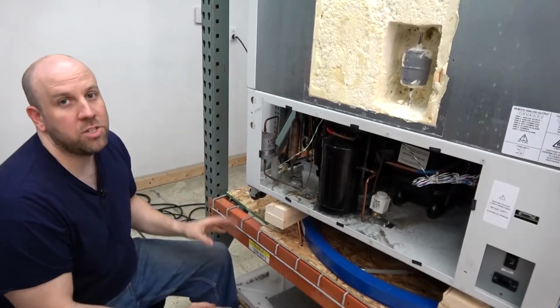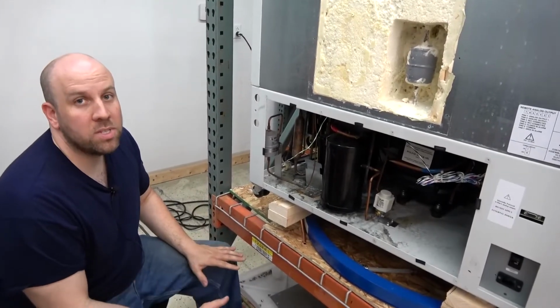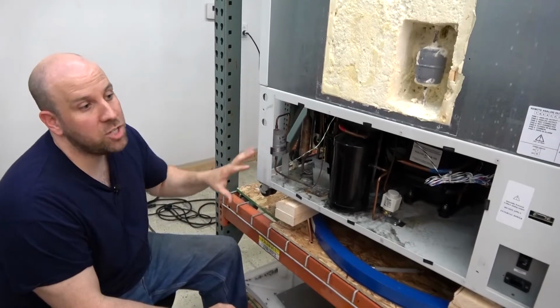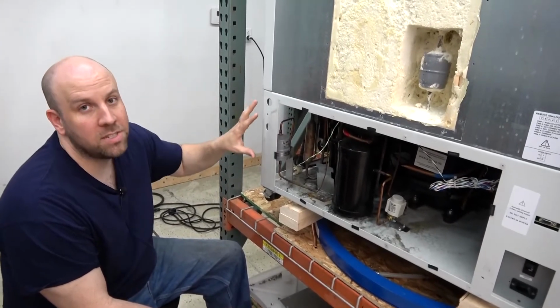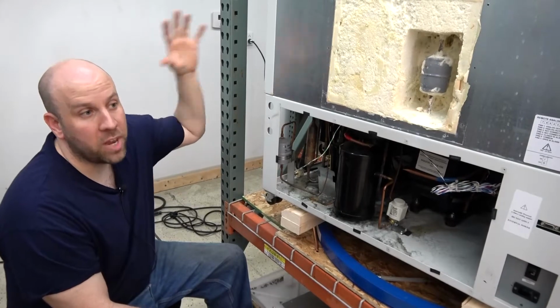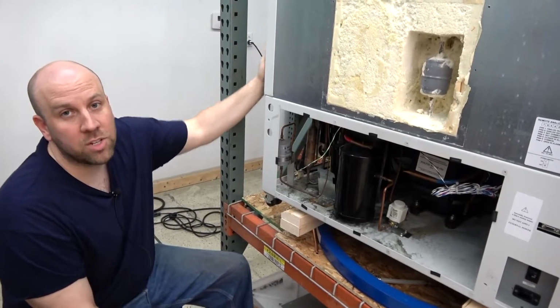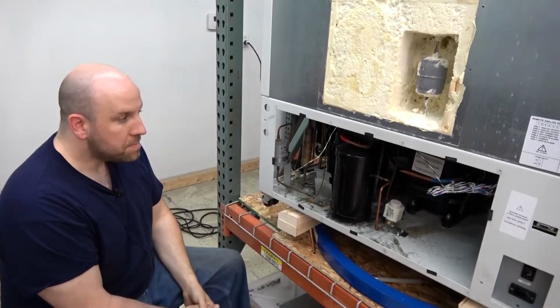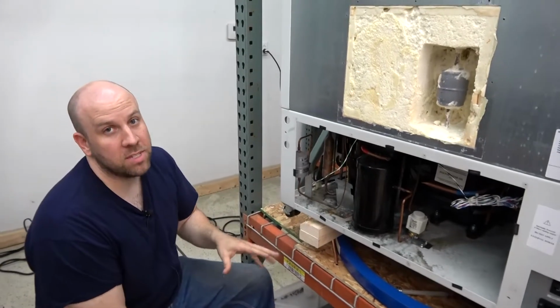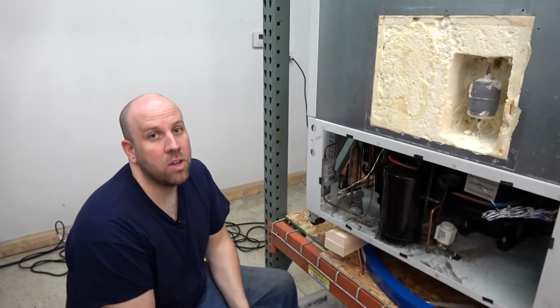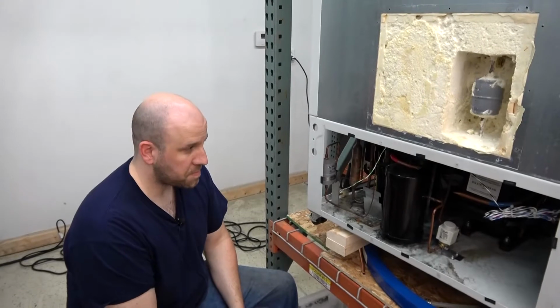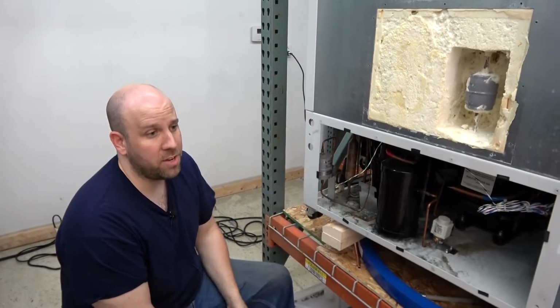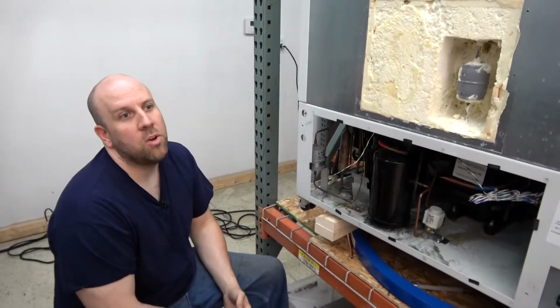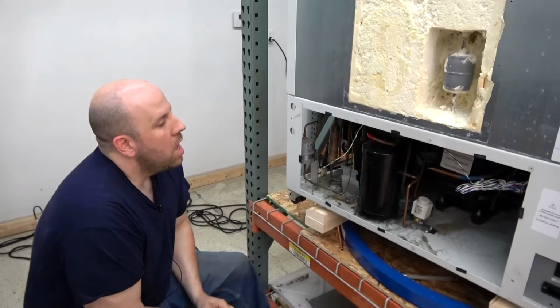There's stage one and stage two. Stage one's only purpose is basically to get stage two condensed into a liquid, cooled, so that stage two can do the main work of actually cooling the unit. So that's one thing really unique about these is the two-stage design. It's called cascading refrigeration, and that's what makes it a lot different than your normal freezers or air conditioning in general.